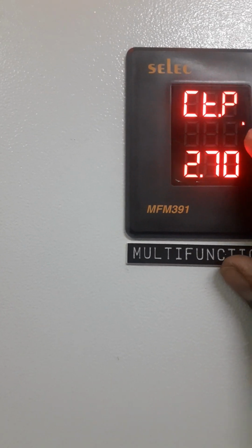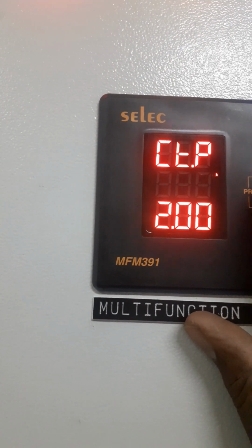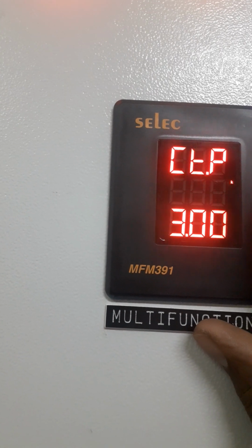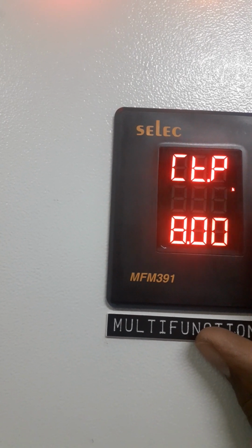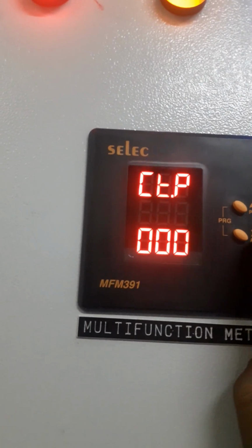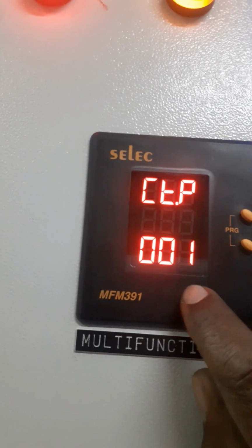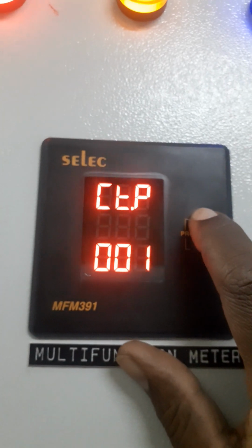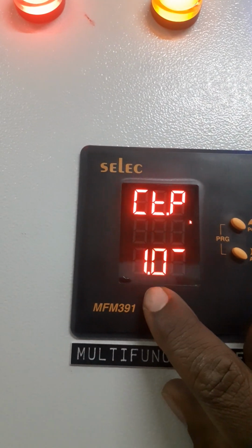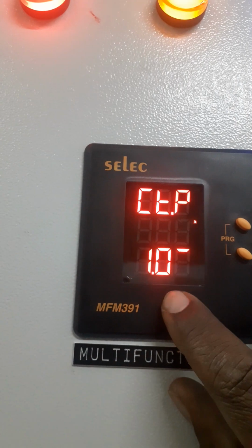I've held until it has started flashing. Then I want to remove this K. I'll show you how I remove that K, because that's where we started. And the K is gone. So in case you come across this, you'll set it to 001, then you have to hold it here for a few seconds, then the K will appear, because in our case we want it to be 2.5 kilo amps, which is 2500 amps.